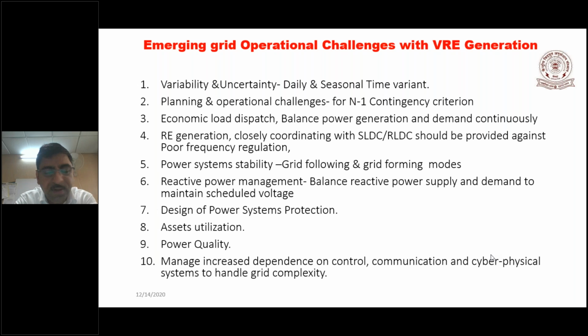In case of wind farms, I have hundreds of machines connected together, and the spread of a wind farm may be 10 to 15 kilometers. So at location A, I get a short circuit current depending on the wind speed input level, and at another location, a different short circuit current. So I have around 100, 150, or 200 short circuit currents clubbed together at the point of common coupling with the grid, all superimposed on each other.